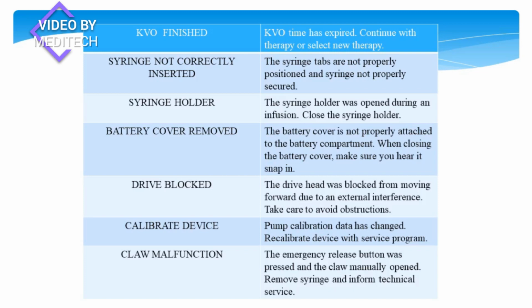Drive blocked. The drive head was blocked from moving forward due to external interference. Take care to avoid obstructions. Calibrate device. Pump calibration data has changed. Recalibrate device with service program. Claw malfunction. The emergency release button was pressed and the claw manually opened. Remove syringe and inform technical.